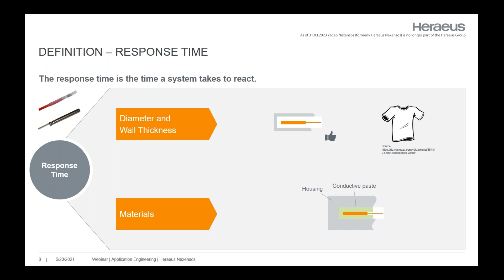So we insert a filling material here, this is an example of conductive paste. In green, you can see that, and that conductive paste improves the response time. You always have to take care of so-called air holes, as those would also decrease performance and response time. We also have to say that the conductive paste is still not an amazing heat conductor, but it's definitely better than air. So that's the example we have here in the picture.